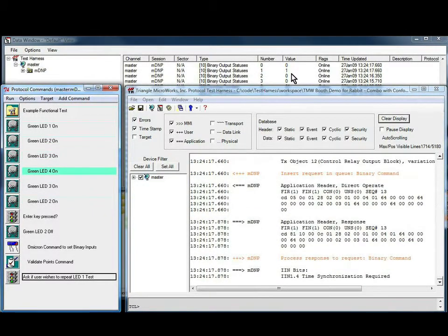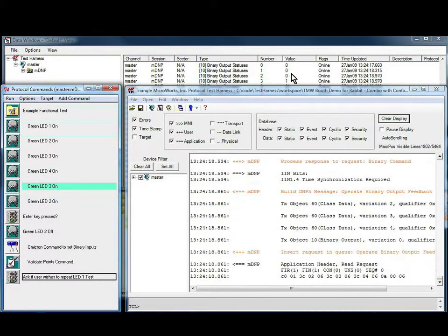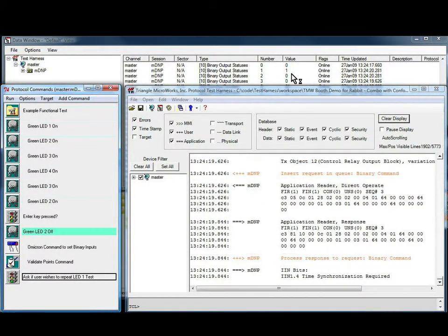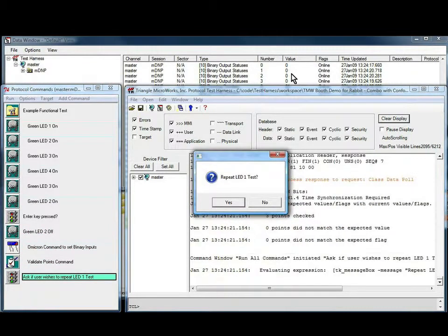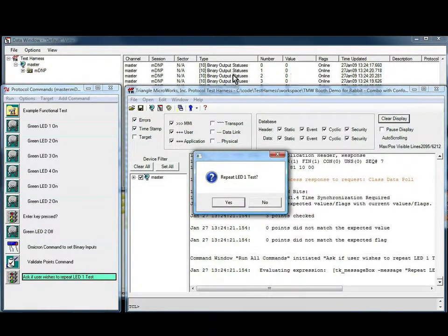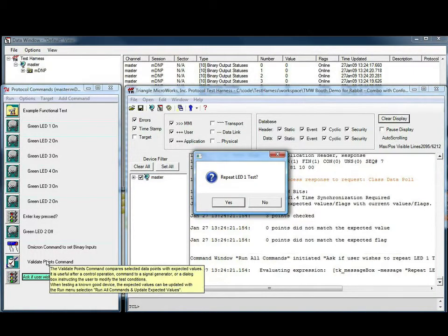If I now press and hold the enter key, execution continues past the conditional command. The Omicron sets up the expected binary inputs and we pass the validate points command, indicated by the fact that the test continued.